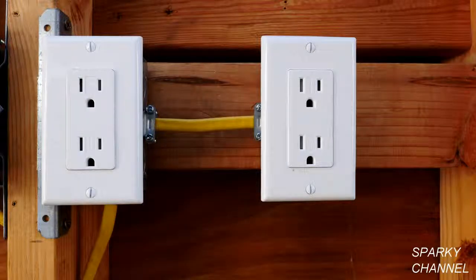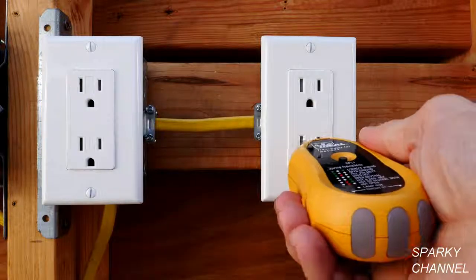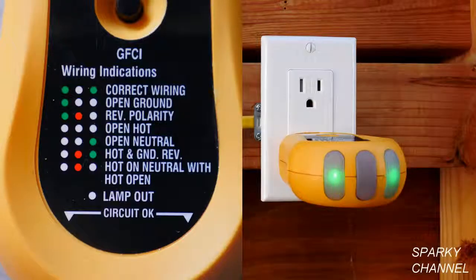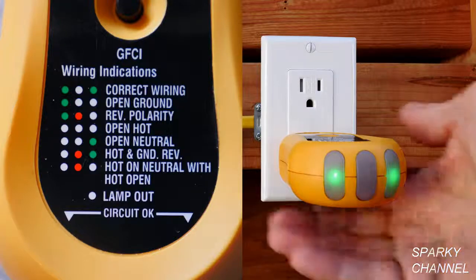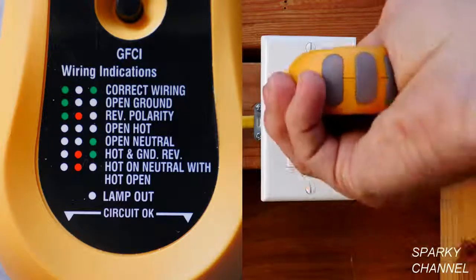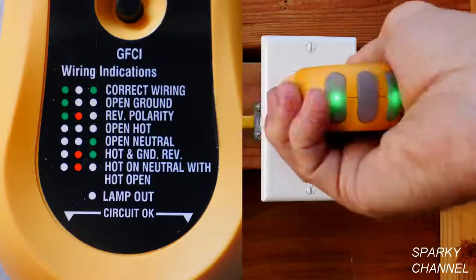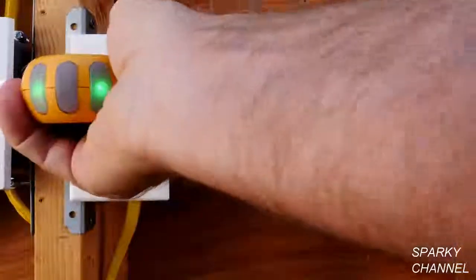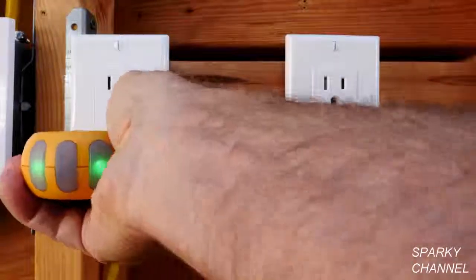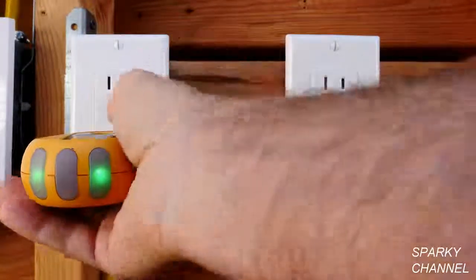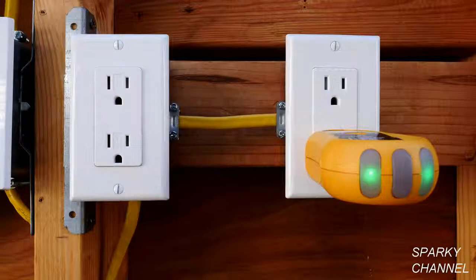Now I've turned the circuit breaker back on, and I'm going to plug my outlet tester into the original receptacle that had the problem, and we have the two green lights that indicate correct wiring. And we'll try it on the other part of the outlet. That works fine, and we'll plug it in over here on the first outlet. That still works fine. So everything works great. So that's how you fix a receptacle that isn't working due to open neutral.